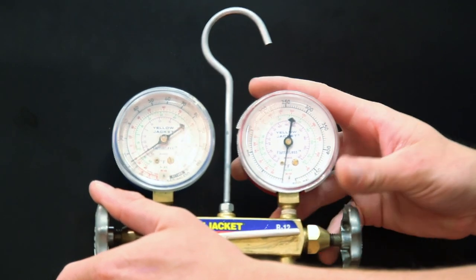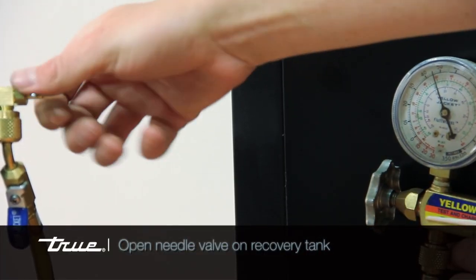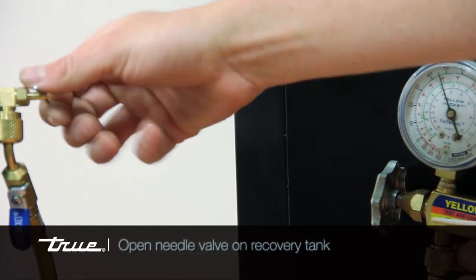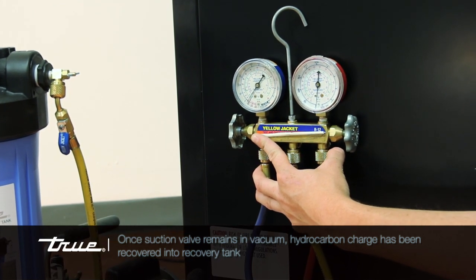Open your refrigeration gauge ports and then open the recovery tank needle valve to allow the refrigerant in the cabinet to be absorbed into the tank filter. Once the suction valve remains in vacuum, the hydrocarbon charge has been recovered into the recovery tank.